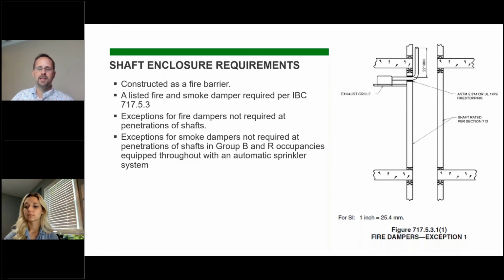And that's something you need to think through on each project and with your AHJ to make sure that interpretation is correct, because we don't have a fire smoke damper. That subduct helps protect against the fire, and that continuous upward airflow helps protect against smoke, because if you have continuous airflow, that shaft is going to be negative compared to all the other spaces, so that's going to be the smoke protection to keep the smoke from traveling between floor to floor. So it's important not to just take this for granted, throw a fan up there, and say we're good without thinking about that continuous portion of the code language.